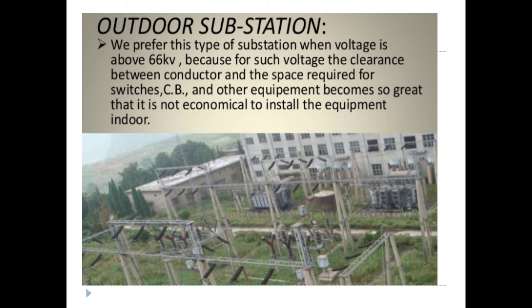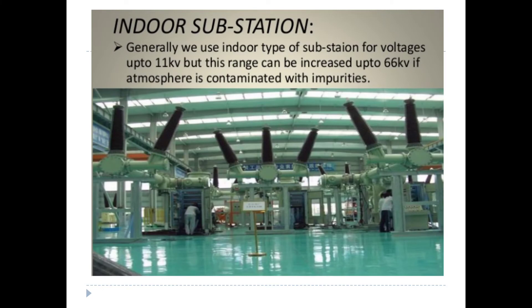The Outdoor Substation and Indoor Substation. For voltages above 66 kV, we prefer the outdoor substation because of the large clearance between conductors and space required. At 66 kV, the space required for the switcher, circuit breaker, and equipment makes it suitable outdoors. The Indoor Substation is used when the voltage is usually up to 11 kV, sometimes up to 66 kV.